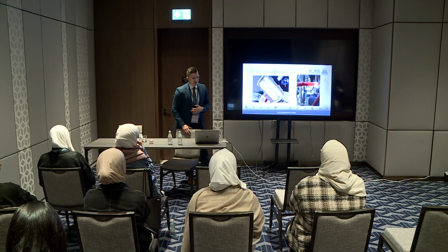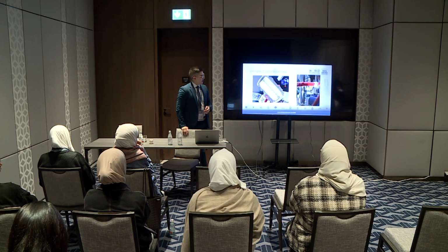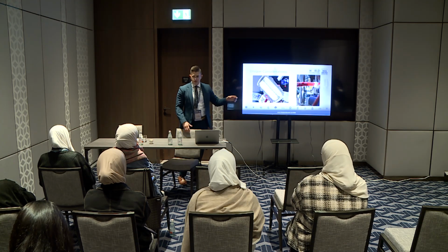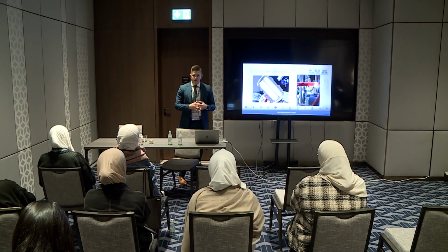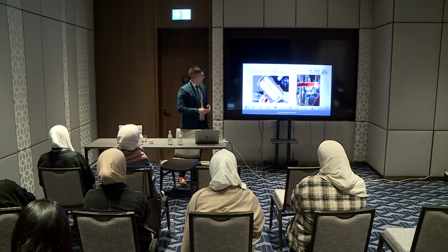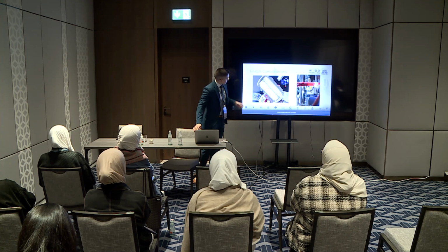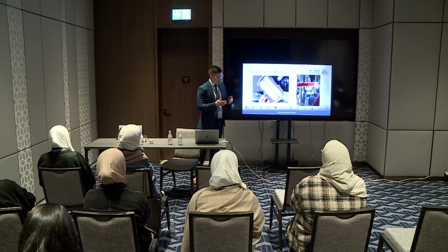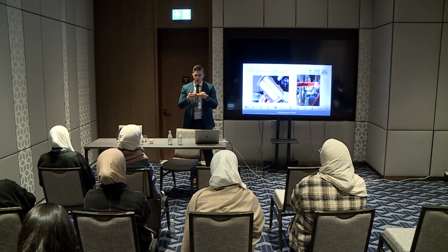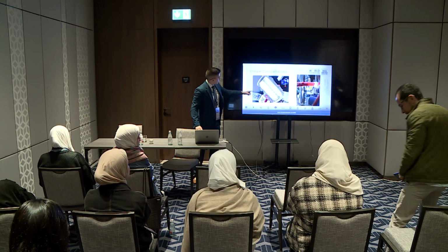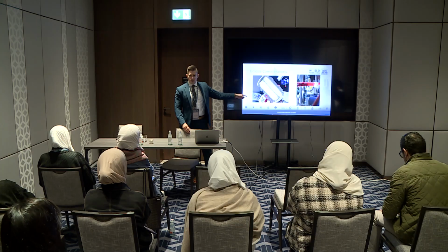And so like we talked about, ECMO provides unique considerations for coagulation management. This is a picture I took a little while ago. This is an oxygenator, the membrane that provides the gas exchange during ECMO. They just sliced it in half, but this is what it looks like on the inside. What you see here is two different chambers. One chamber has just the oxygenator fibers, very, very small fibers where gas passes through. As the blood passes across the fibers, the gas exchange occurs across them. But you can see how densely packed these fibers are in these devices.